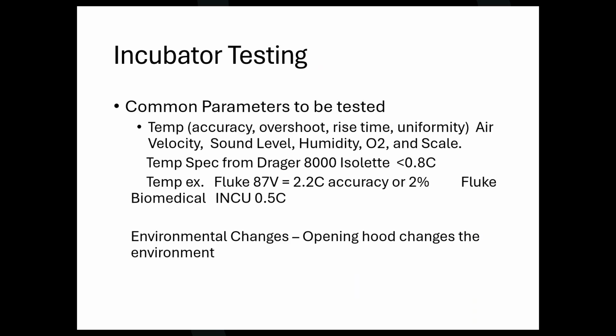The other thing to think about every time is this: what happens every time you open and close that incubator? The temperature changes. I'll even go one further: the environment changes. I will tell you, when we go on site to do calibrations, we have to warm up our equipment for about 30 minutes before we can start doing calibration. So whoever comes, you'll see them turn it on first thing and do all of this stuff.